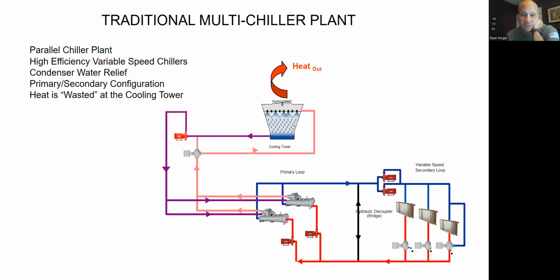So these air handlers take heat out of the air, right? Remember we said it's pretty standard to have 44-degree water going out and 56 or 55 or 54-degree water coming back to the chiller, right? That's what it's doing. So these coils are sending me cold water. I'm adding heat from the space to the coil, and I'm sending warmer water back to the chiller. And the chiller's job is to cool that water down with the refrigeration cycle and send cooler water back.